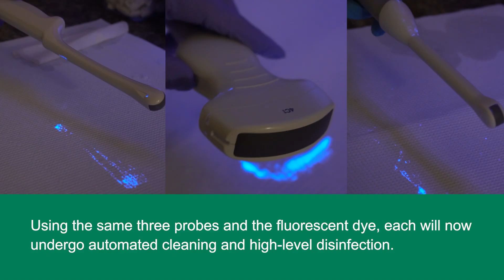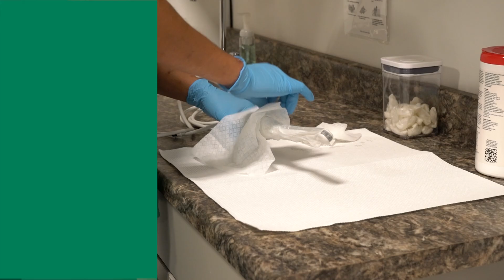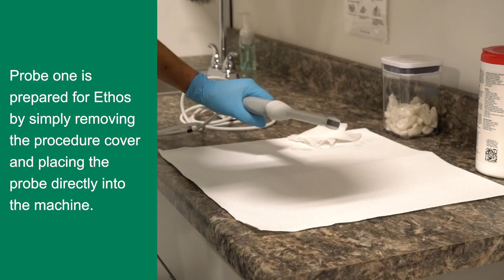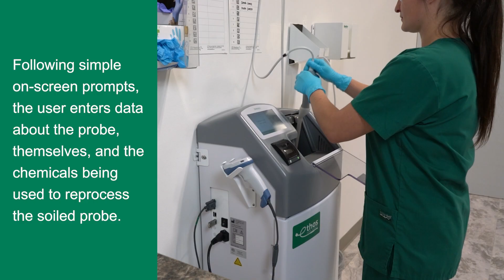Using the same 3 probes and the fluorescent dye, each will now undergo automated cleaning and high-level disinfection. Probe 1 is prepared for Ethos by simply removing the procedure cover and placing the probe directly into the machine. Following simple on-screen prompts, the user enters data about the probe, themselves, and the chemicals being used to reprocess the soiled probe. Once data is entered, Ethos automatically cleans and high-level disinfects the ultrasound probe.